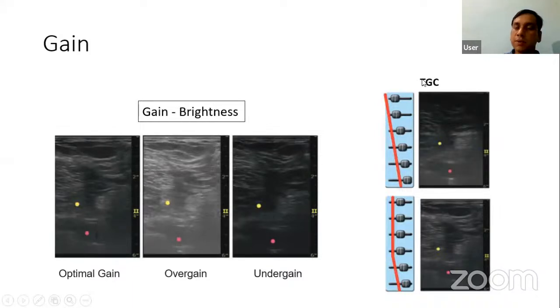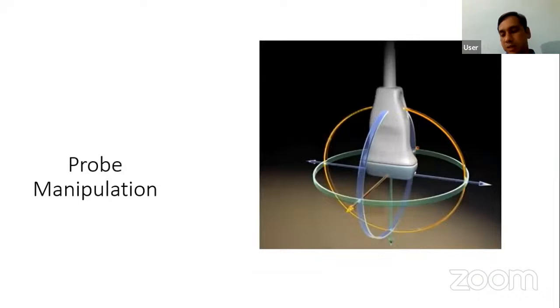So what is TGC? TGC stands for time gain compensation. Basically, because there are different structures at different levels, there are certain machines with different toggles that you can keep on adjusting to adjust the brightness at different levels. So you can have a good view of different structures present at different depths. Different machines have different knobs for it. Some machines have five toggle switches where you can adjust it to get a good view of different structures present at different depths. Now, these are the ways you are going to use the knobs to improve the image.